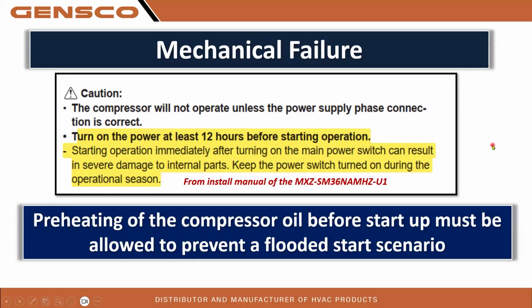How many of you are aware, I hope you all are, that you must heat these compressors up before you turn them on, especially the first time? It requires 12 hours of power before running so that the crankcase heat function, which is a function of the inverter, heats the windings of the compressor in order to heat it up.